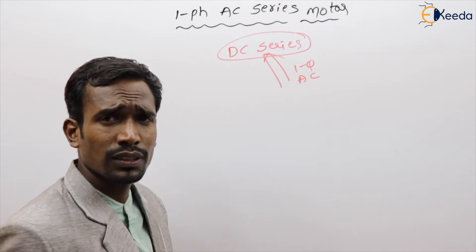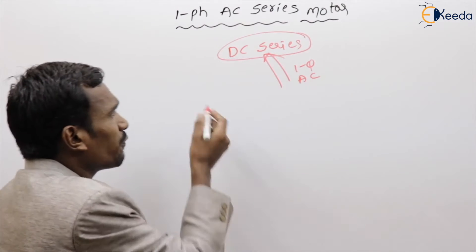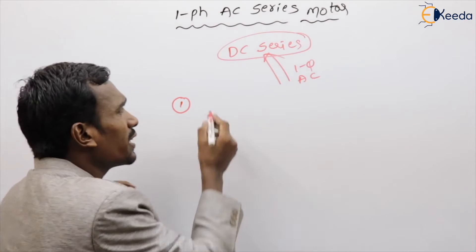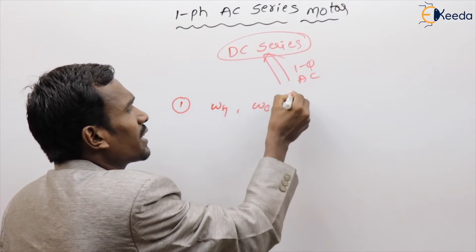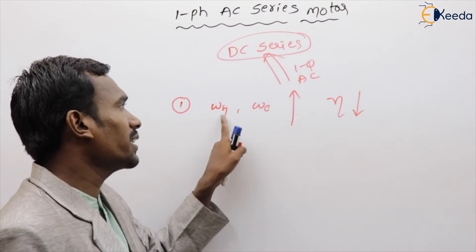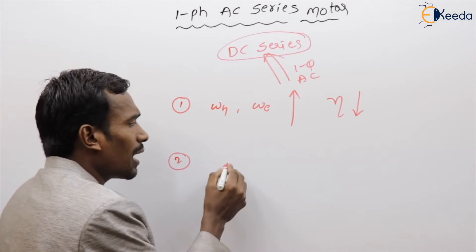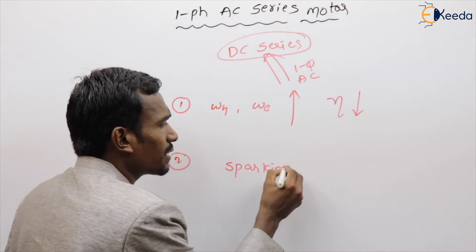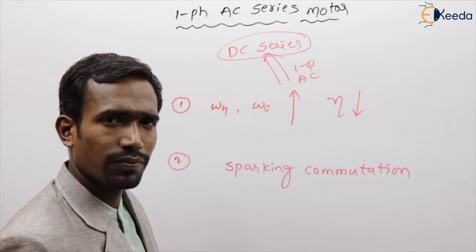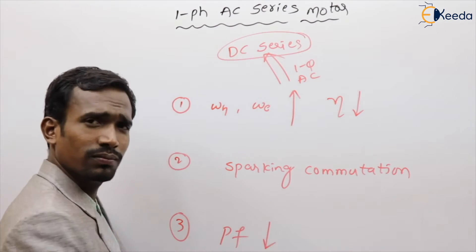When you give single-phase AC supply to a DC series motor, there are difficulties. The first difficulty is that hysteresis and eddy current losses increase, and efficiency decreases. The second difficulty is commutation sparking.